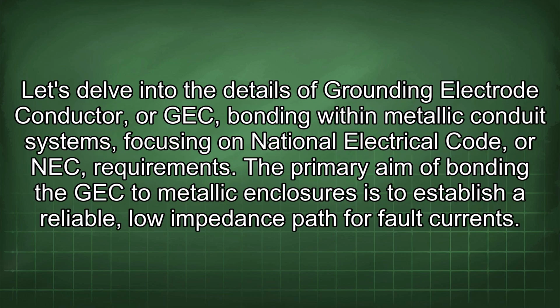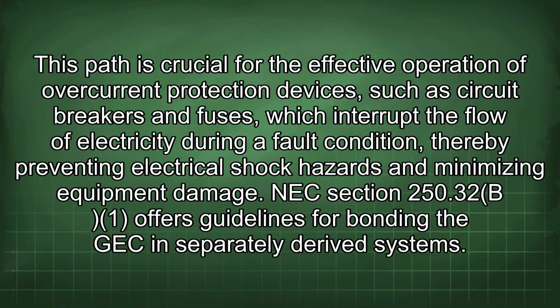Let's delve into the details of grounding electrode conductor, or GEC, bonding within metallic conduit systems, focusing on National Electrical Code, or NEC, requirements. The primary aim of bonding the GEC to metallic enclosures is to establish a reliable, low impedance path for fault currents. This path is crucial for the effective operation of overcurrent protection devices, such as circuit breakers and fuses, which interrupt the flow of electricity during a fault condition, thereby preventing electrical shock hazards and minimizing equipment damage.